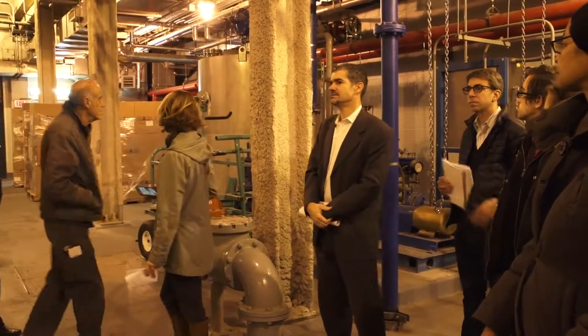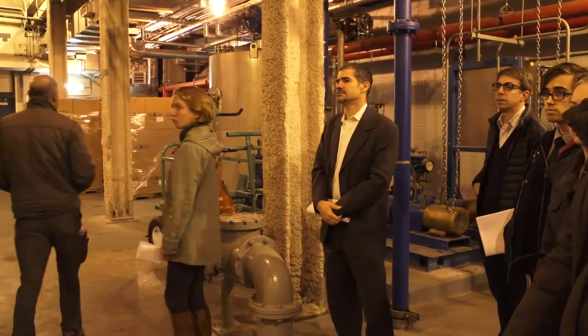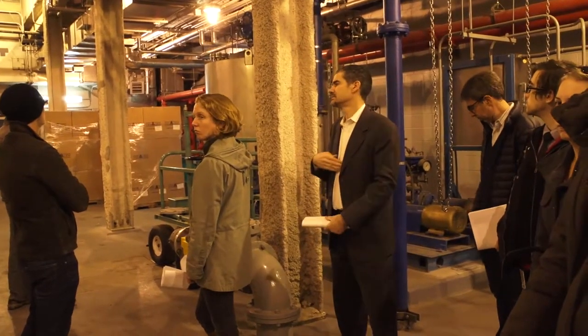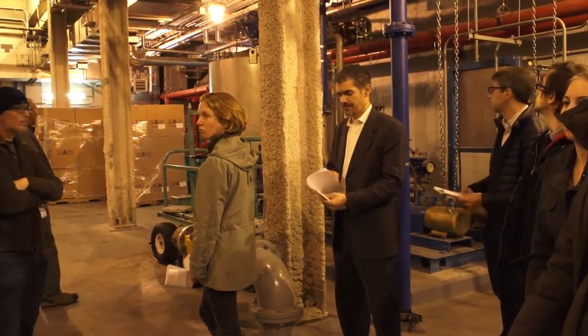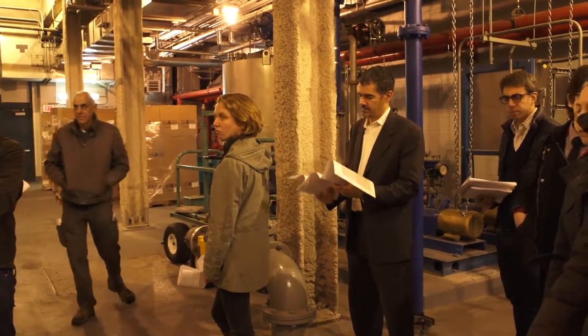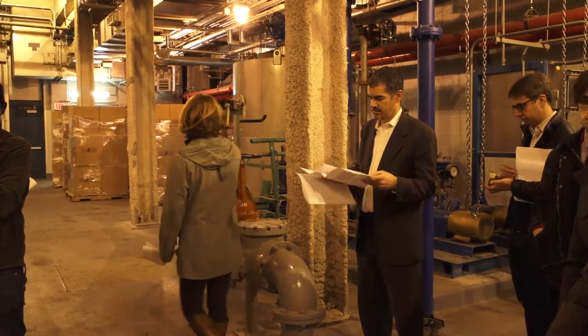That is a break water tank. What we do is, the process areas can't cross-contaminate fresh water. This entire building is protected by that tank. If I have a hose leaking or some sort of vacuum in the water system, it won't suck up sewage or some sort of dirty water back into the system. We use this break tank to prevent that.